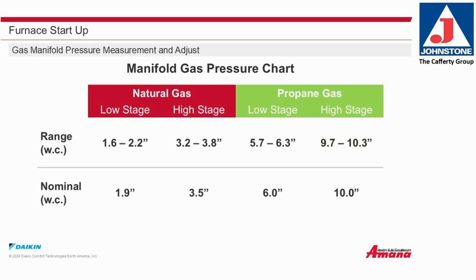Gas manifold pressure measurement and adjustment. The manifold gas pressure range for natural gas is low stage 1.6 to 2.2 inches of water column, high stage 3.2 to 3.8 inches of water column. Nominal would be 1.9 low stage, 3.5 inches high stage. For LP, 5.7 to 6.3 inches water column for low stage, 9.7 to 10.3 inches for high stage. Nominal would be 6 inches low stage, 10 inches high stage.